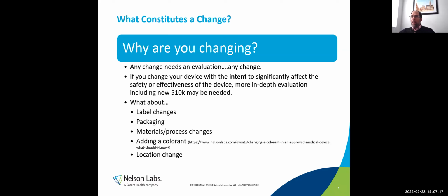But to know when to submit a new 510K is important, because obviously then you're talking to a different audience. You're not just talking to maybe an auditor that's coming through. You're talking to a reviewer, a biocompatibility expert. So you might need to have a little bit more in-depth communication about those types of changes.